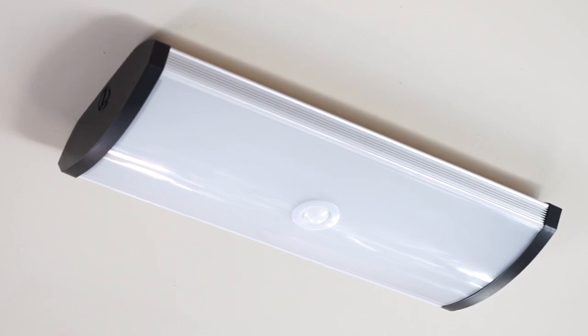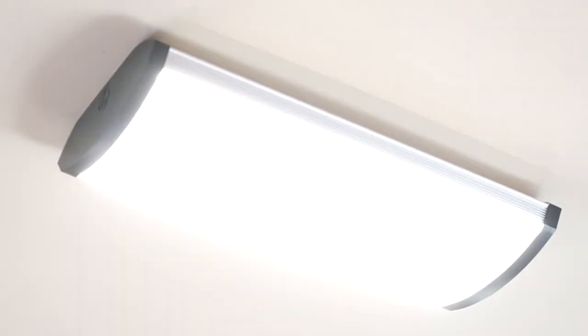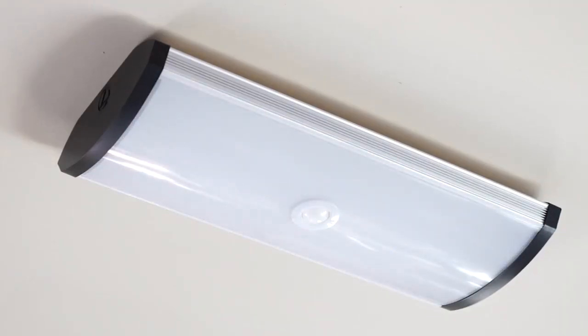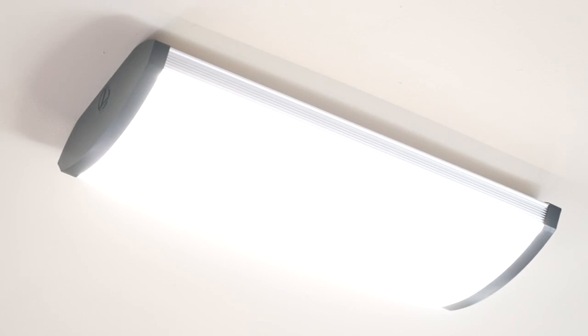Turn on the electricity at the circuit breaker box and walk back into the room where the fixture is installed. The light will turn on automatically as soon as motion is detected in the room by the PIR sensor. Verify the PIR sensor is working properly by exiting the room and wait to see if the light turns off in the selected time frame.